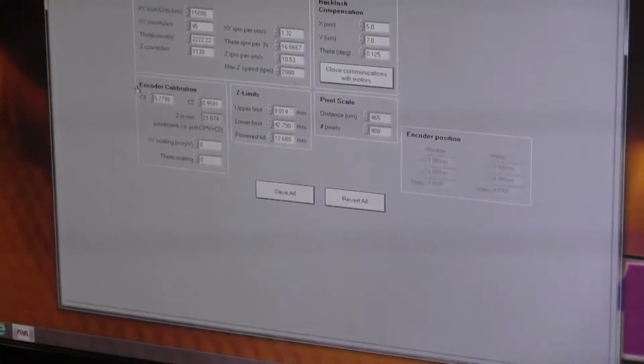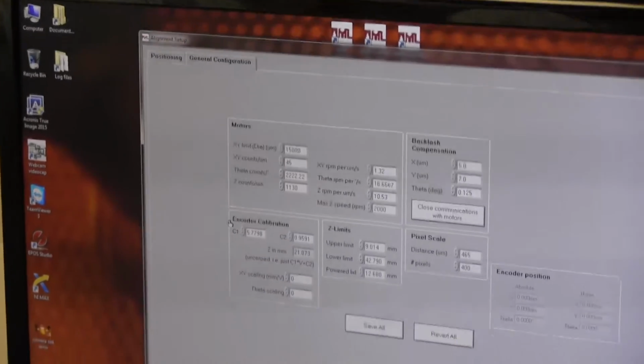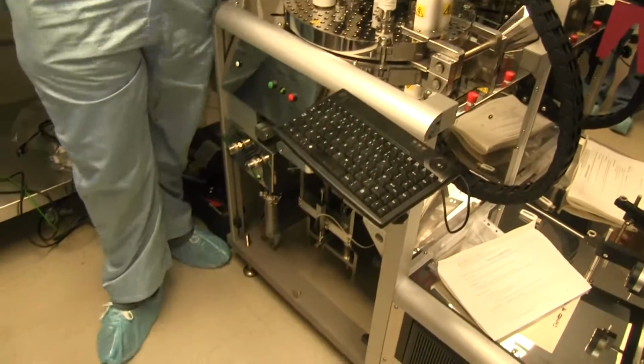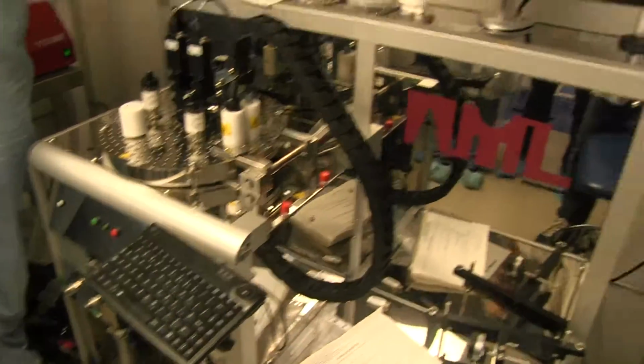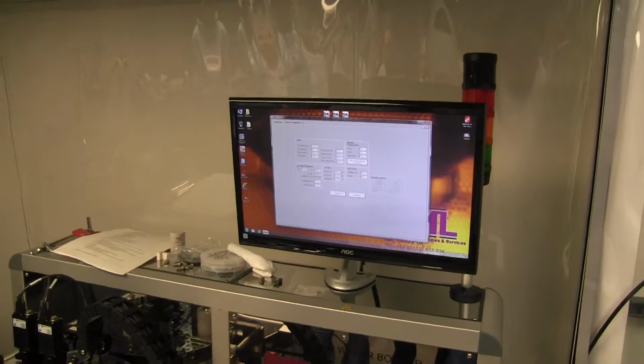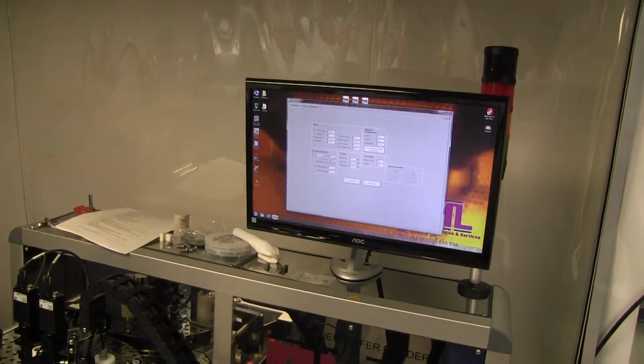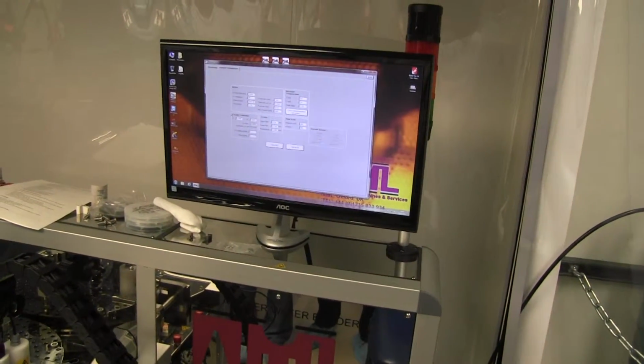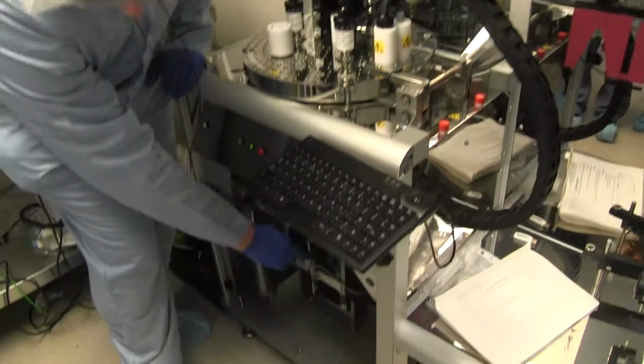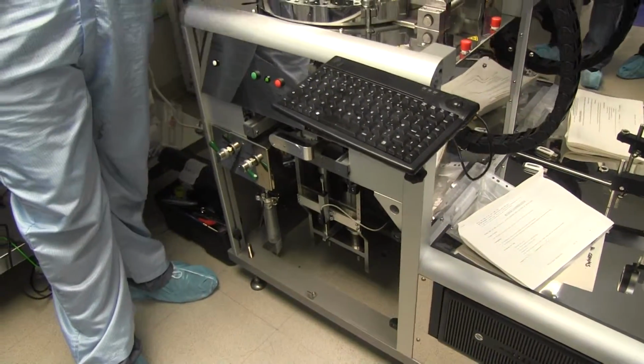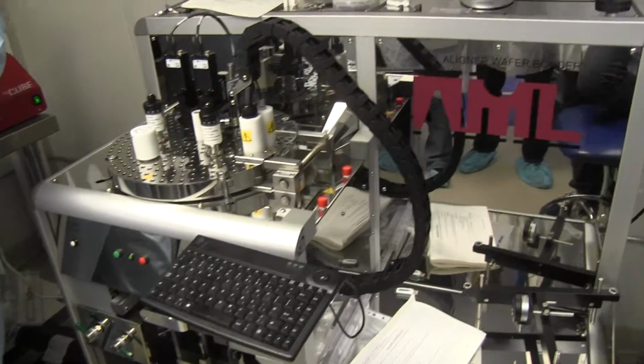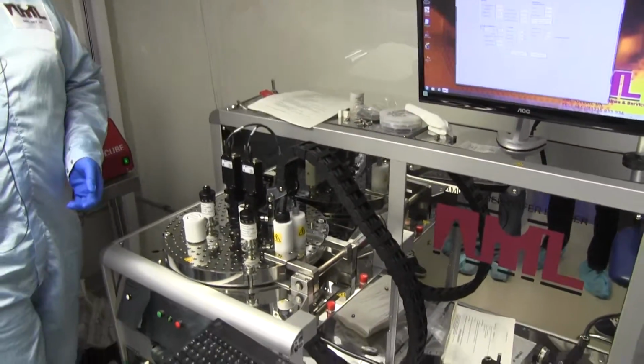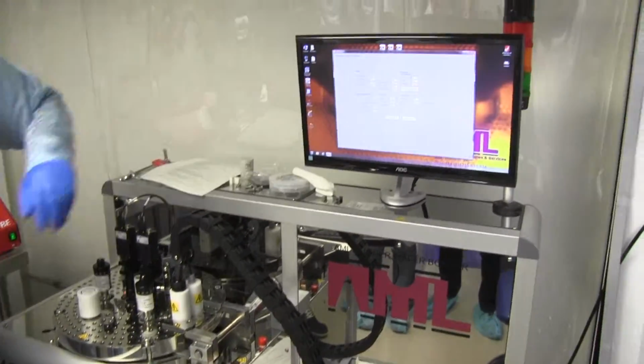Encoder calibration. This encoder here, that's how the software is able to tell what height the manipulator is at. So how far, and it uses that height to calculate wafer separation. The response from each of these that we buy in is slightly different. So we measure those versus a micrometer, plot the graph, get the calibration coefficients, and they go in here.